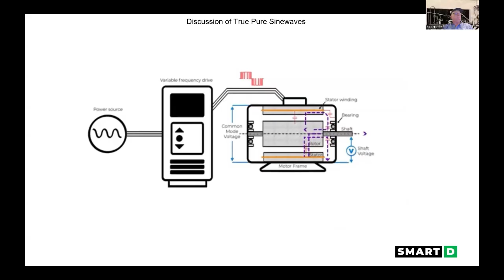If the motor frame is poorly grounded and the motor is connected to a mechanical load that has proper grounding, low impedance, the common mode current flows through the shaft, reaching for the lower impedance.